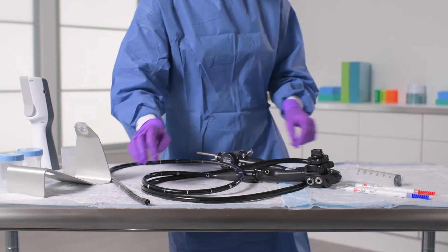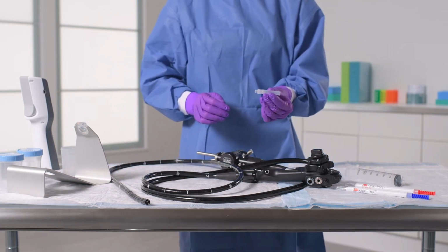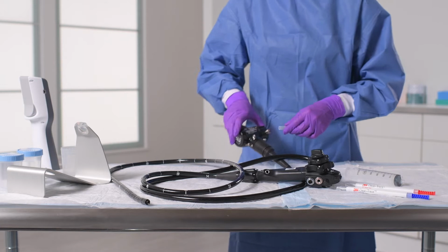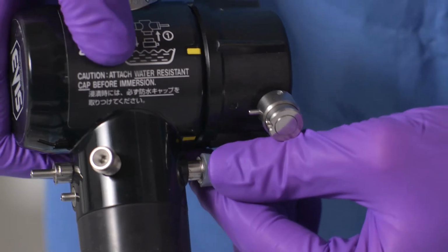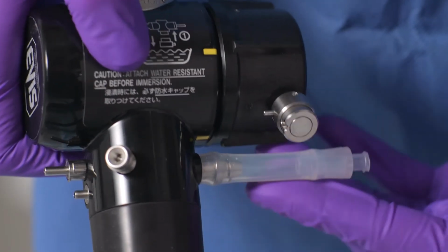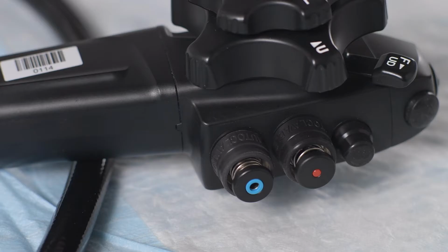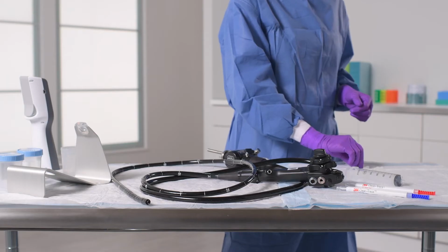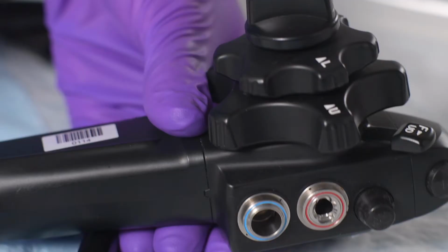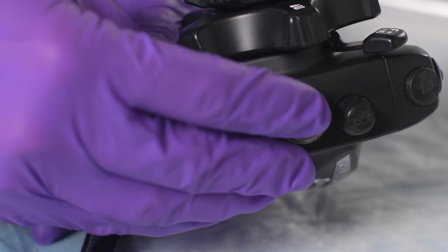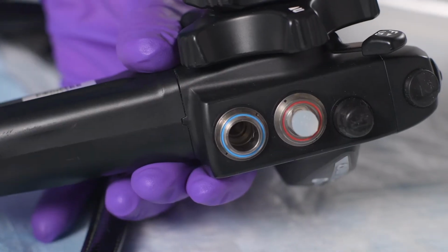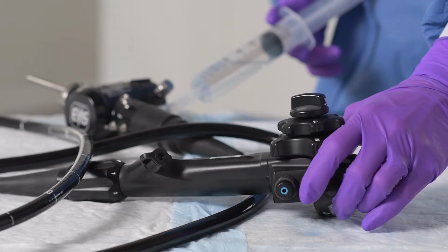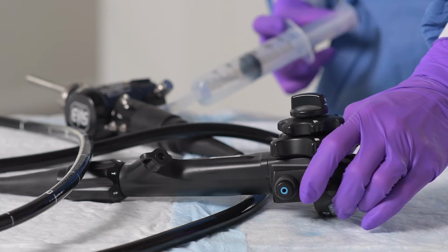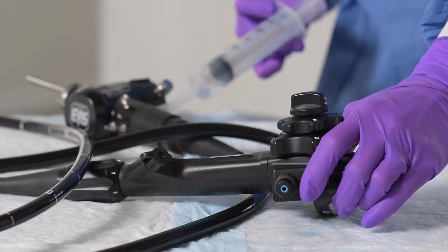To prepare the endoscope for sampling, you'll need a connector from the 3M water test kit. Attach the connector to the barbed hose fitting on the light guide end of the universal cord, sometimes referred to as the Christmas tree. For the suction biopsy port on the control head, you will need to make sure the suction biopsy valve is in place. Or, for Olympus brand scopes, you can use a plug from the 3M water test kit to insert into the suction port. With the plug, you will free one of your hands since you will not need to press down on the suction valve, but it is really a matter of preference.